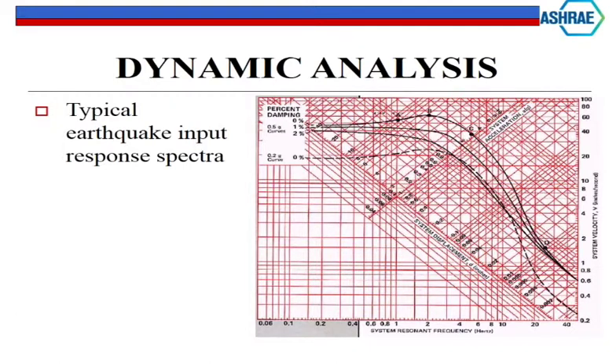And what they'll do is they say, okay, we're going to start with a system acceleration based on an analysis somebody has done in the past. They say, all right, we're going to start with 0.4. We run out to there, and then it comes down to where the system displacement is. And then from the system displacement, we figure out what we need in the way of a spring rate to move that load down to the load that we can go ahead and work on.